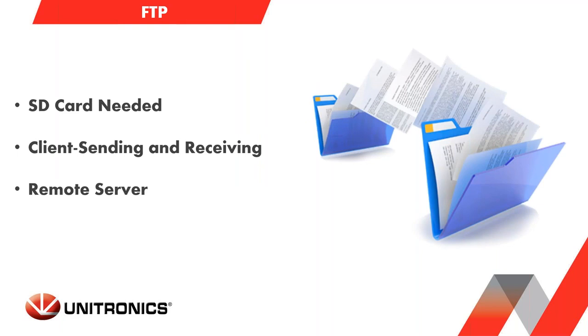Lastly, before we begin some demonstration, we'll discuss File Transfer Protocol, or FTP. FTP is a communication protocol used for transferring files from a server to a client over an Ethernet communication. Data tables, sampler logs, PDFs, and CSV files can be shared between devices over the FTP network. Since the UniStream can act as either a client or a server, you can build your application to log your data directly to your third-party FTP server, or alternatively, you can use a third-party FTP client to connect to your PLC's SD card where the logs have been stored.